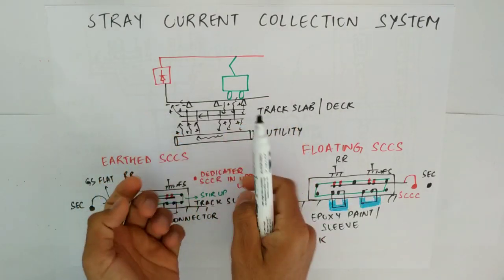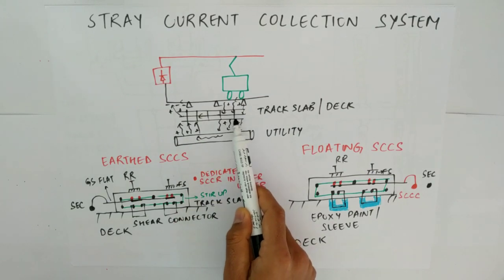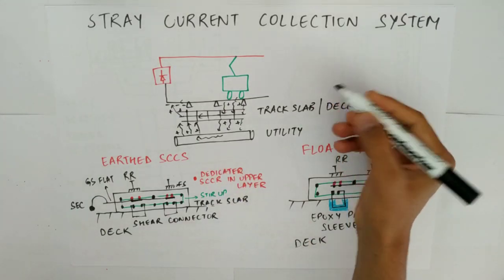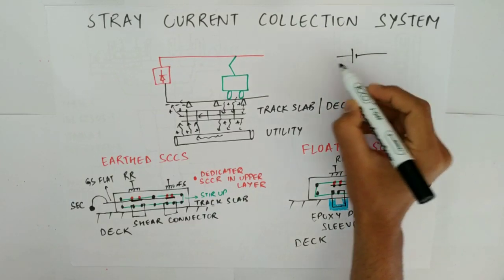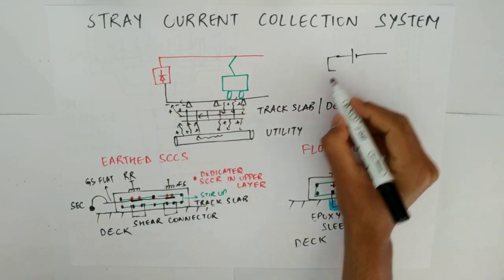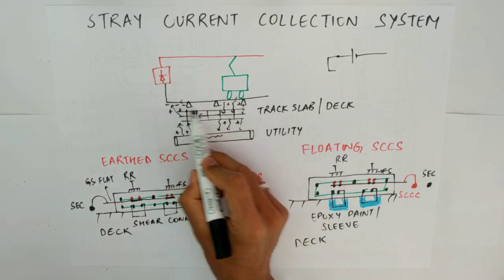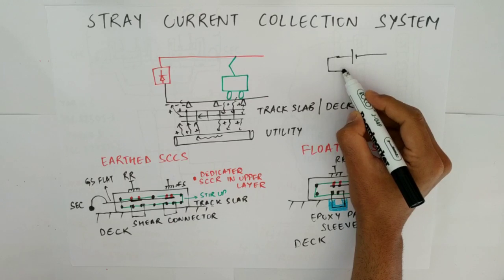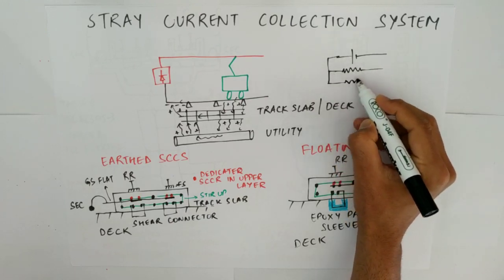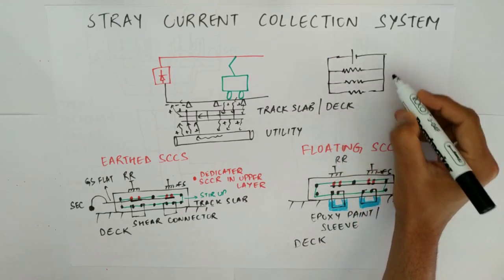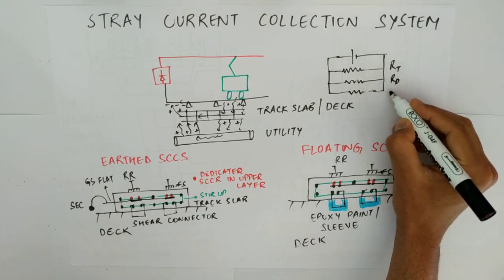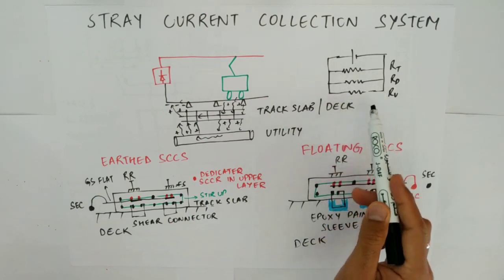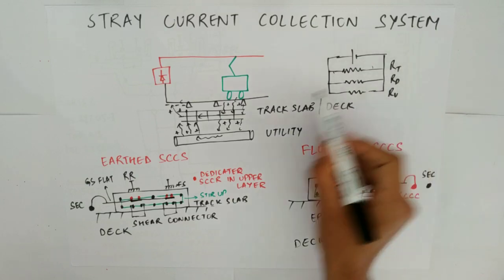The SCCS will catch the stray current which is leaking from the running rails in this stray current collection net and not allow the current to leak further down. Now if we draw a circuit diagram — this is your potential which is causing the stray current. Once the stray current is leaking due to running rail potential, it enters the system, goes into the track slab, then into the deck, and from here further into the utility. So in order to keep the current flowing in the track slab itself and not letting it go below, we can reduce the resistance of the track slab.